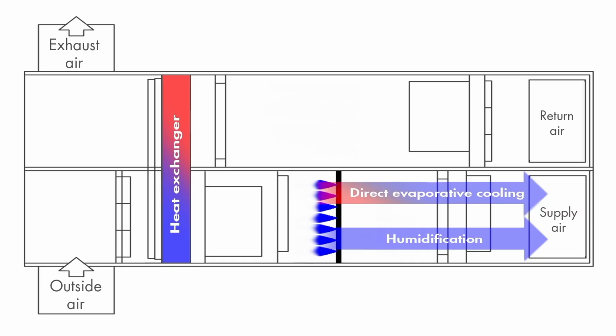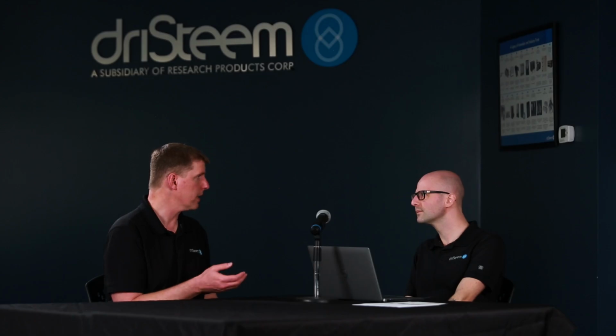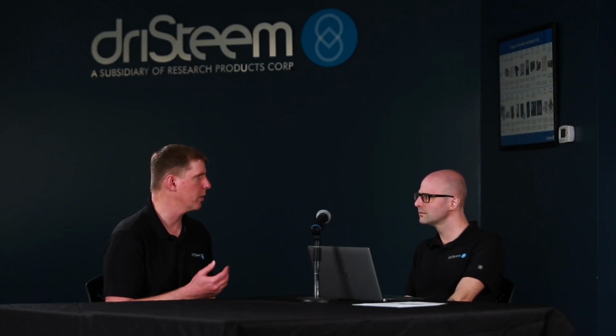If you want to use it for the cooling application, put it before your mechanical cooling system, like a chilled water coil or a DX coil as an example, because you can use that as the first stage of cooling. It may be more practical to do it with water to add the moisture in addition to get the cooling effect so you can run your compressors less. And just a more efficient, extending an economizer season as an example. When economizer, we're bringing outdoor air because it's nice, and maybe we can do it a little bit more because we're conditioning it by adding a little bit of moisture and cooling it before getting into the cooling system.